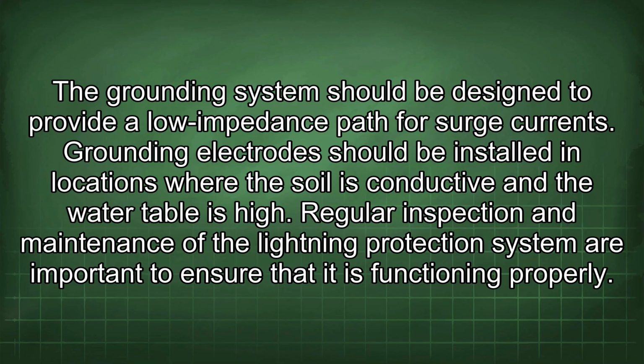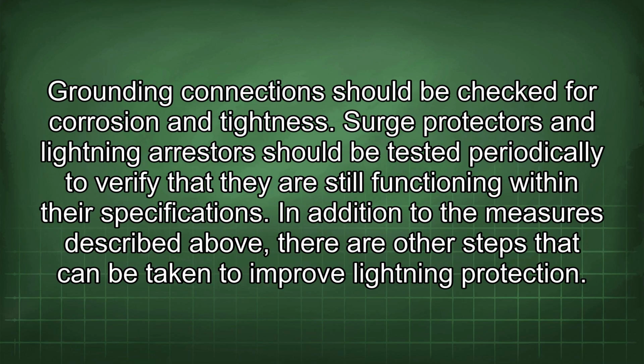Grounding electrodes should be installed in locations where the soil is conductive and the water table is high. Regular inspection and maintenance of the lightning protection system are important to ensure that it is functioning properly. Grounding connections should be checked for corrosion and tightness. Surge protectors and lightning arresters should be tested periodically to verify that they are still functioning within their specifications.